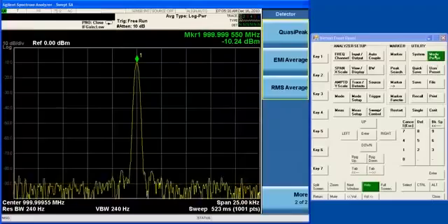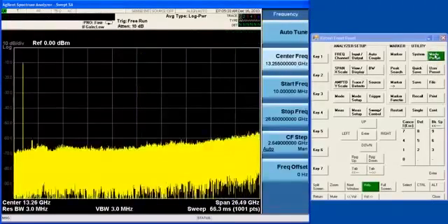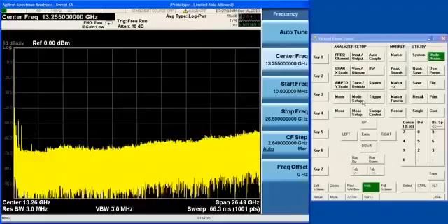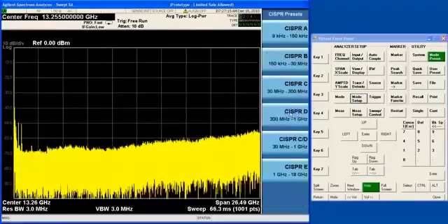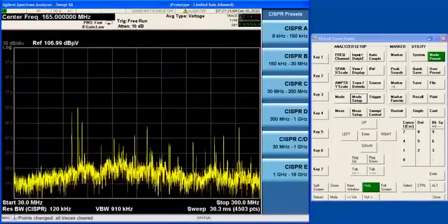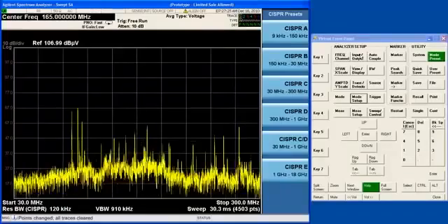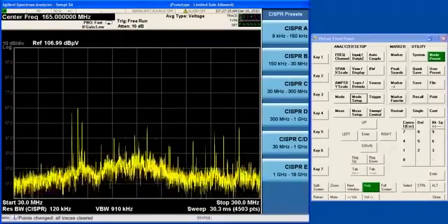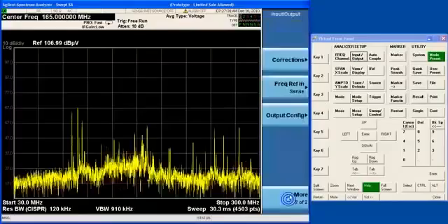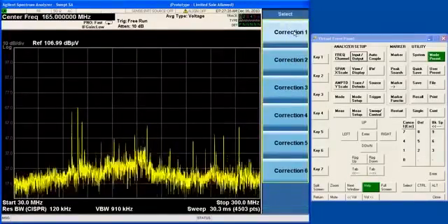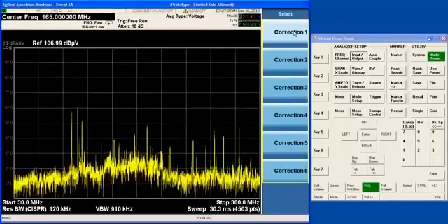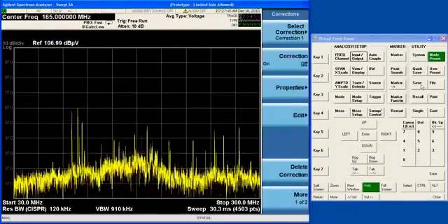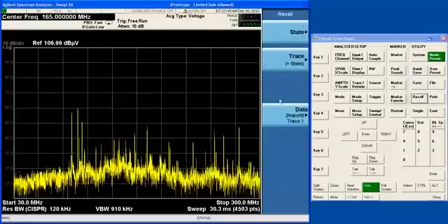Okay, let's go back to the antenna and let's go back to our band C CISPR preset. And I am going to show you the limit line and amp cor capabilities of the X-Series. So, you can load amplitude corrections. The analyzer supports up to six corrections simultaneously.